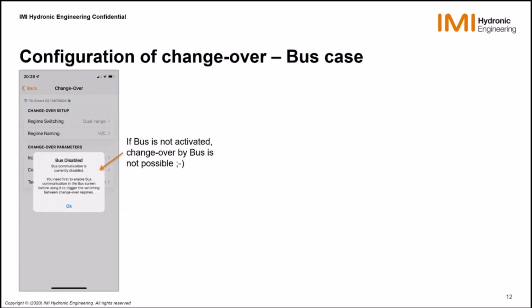If you do the configuration of changeover with bus system, and you have not activated your bus first, it will tell you, I'm sorry, but your bus communication is currently disabled, and you need first to go to the bus communication screen and activate the bus, enable the bus system, to then allow using the bus for switching between the changeover regimes.